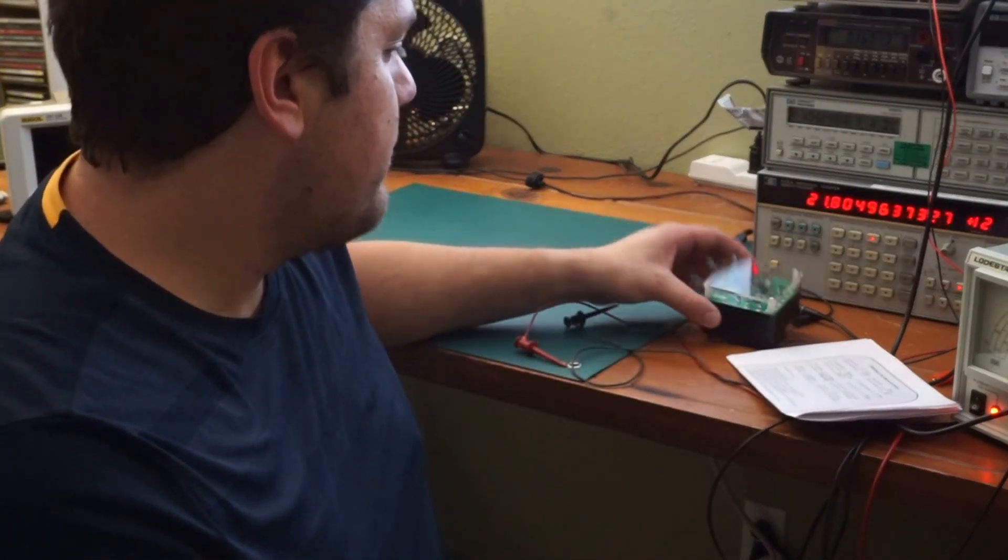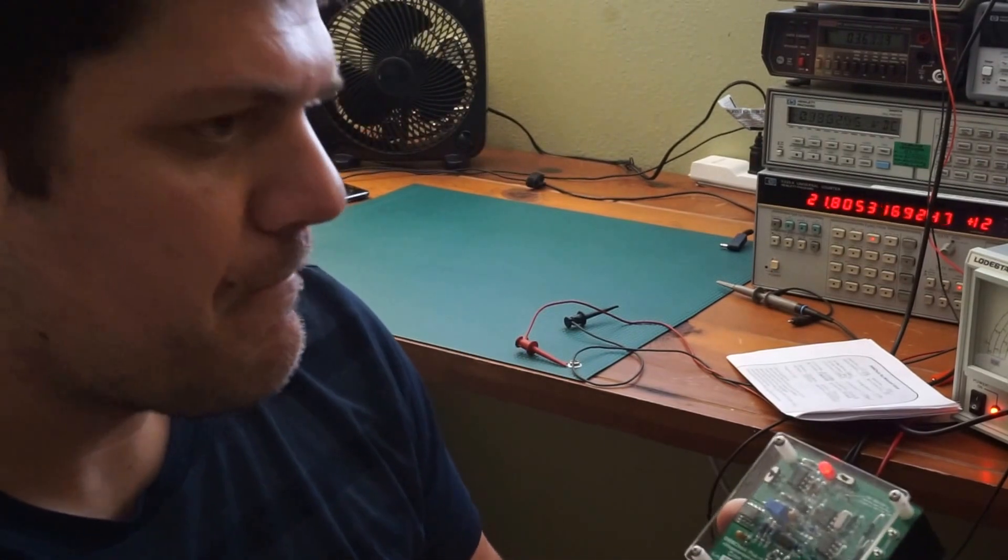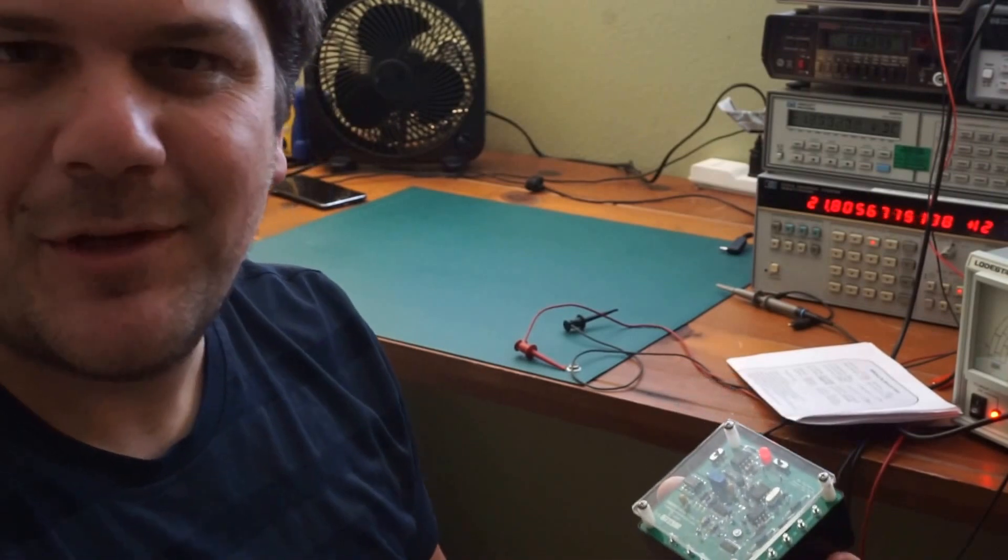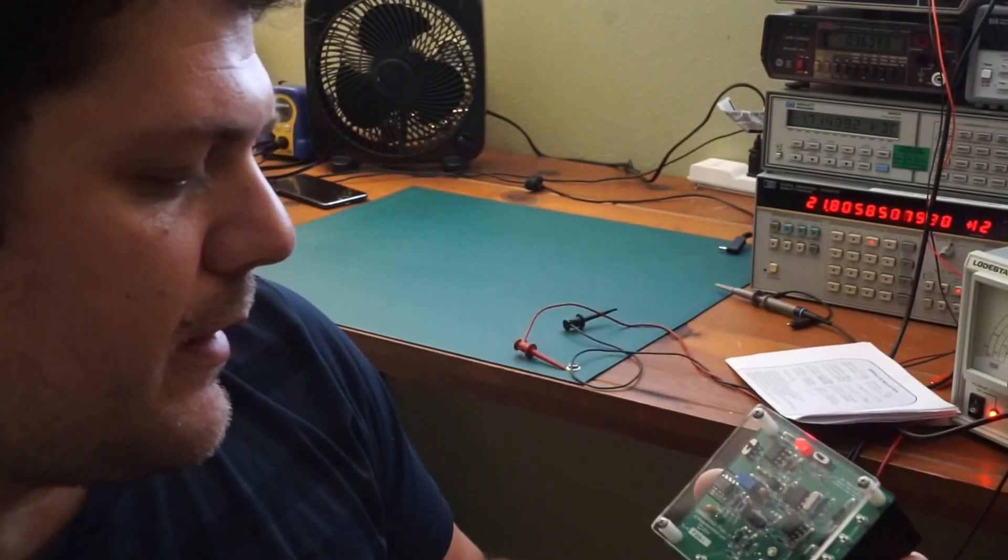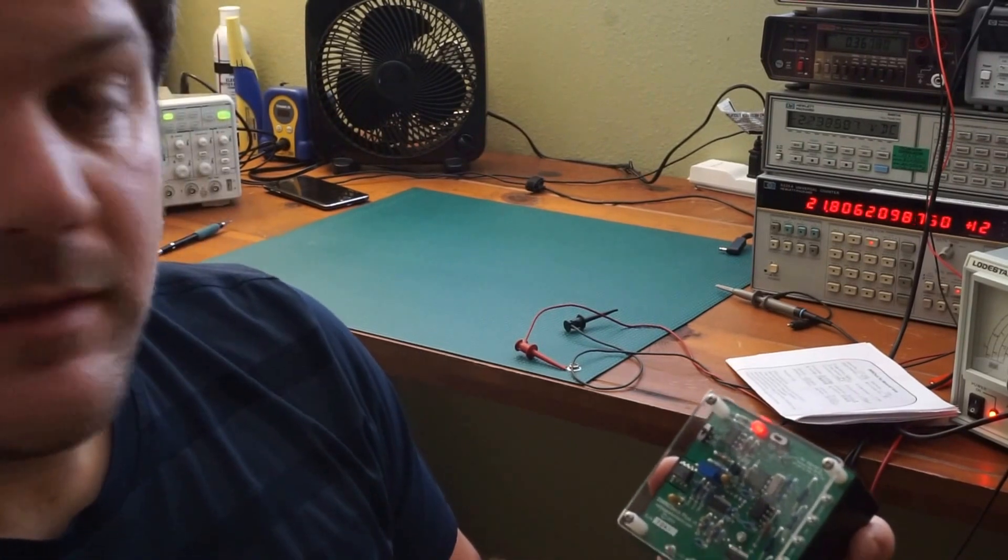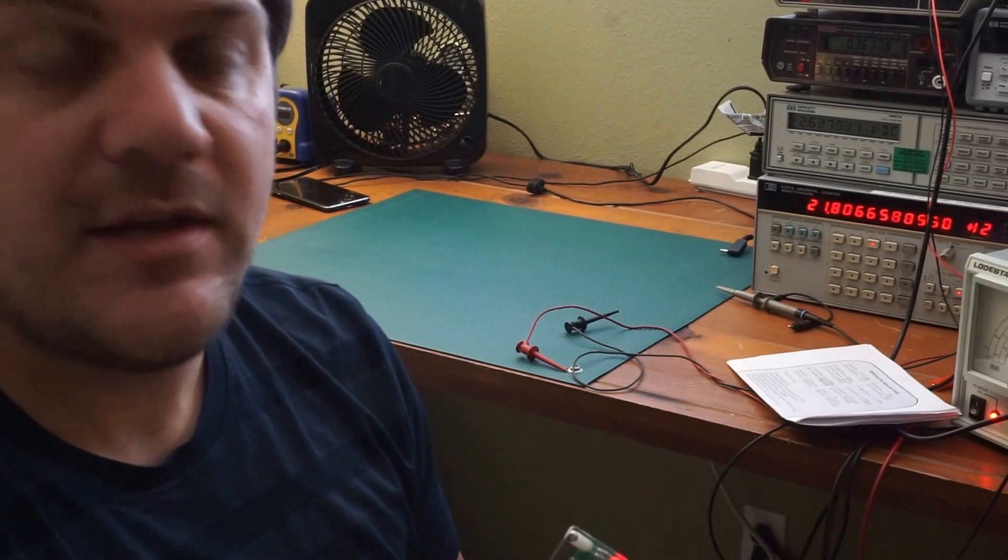I would say this is a pretty multi-featured multimeter calibration tool if you will. It handles AC and DC voltage, it handles frequency, duty cycle, AC-DC amperage and resistance for its tests.